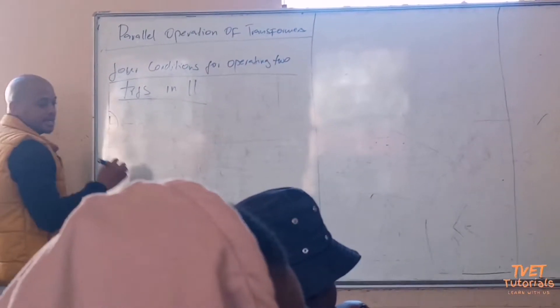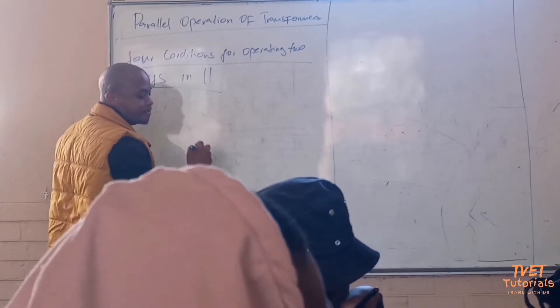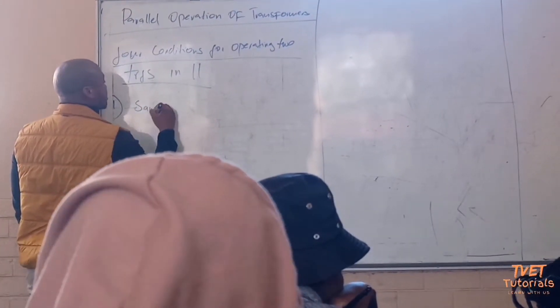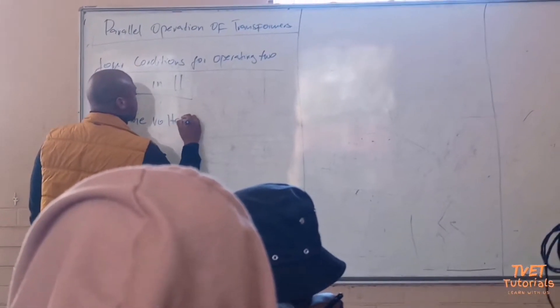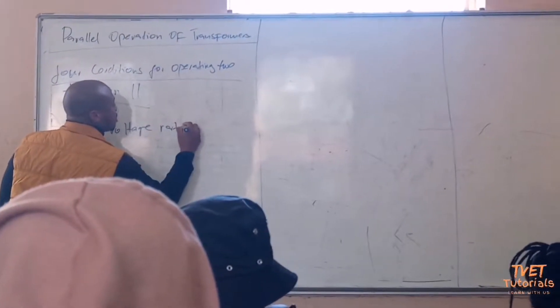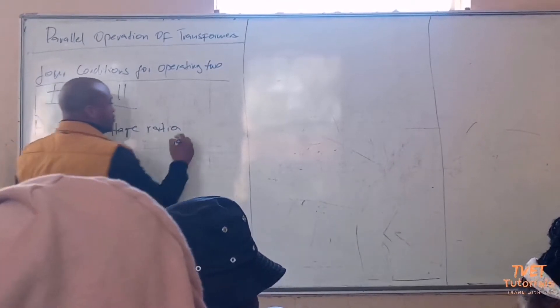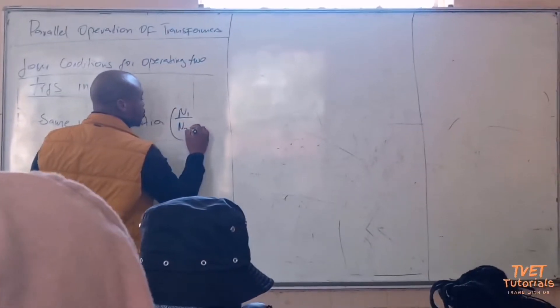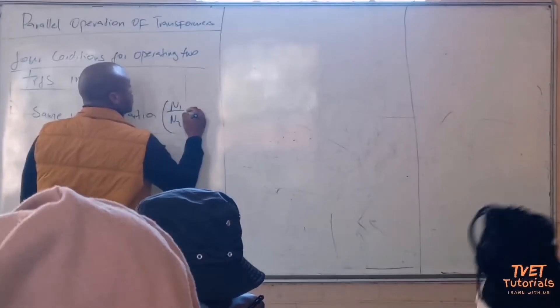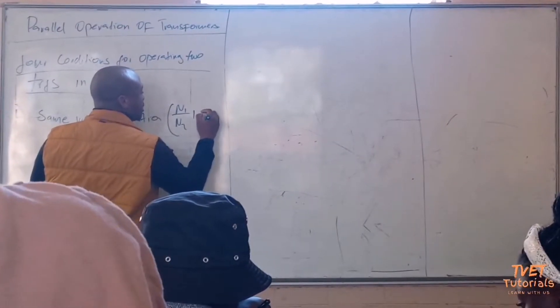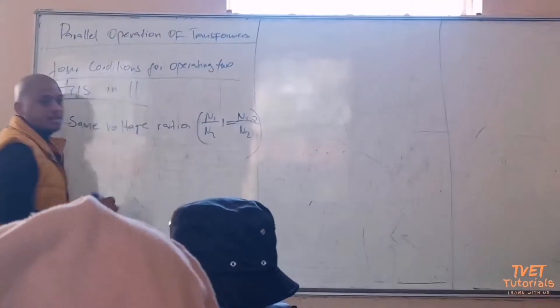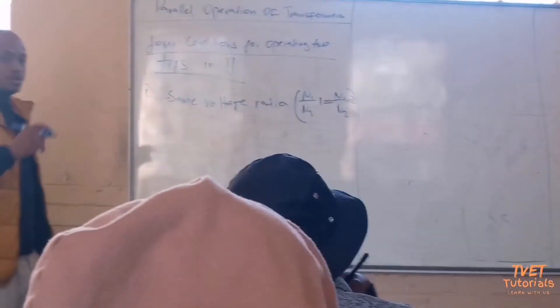The first condition is that they must have the same voltage ratio. They must have the same voltage ratio, meaning that N1 over N2 from transformer number one must be equal to N1 over N2 from transformer number two.